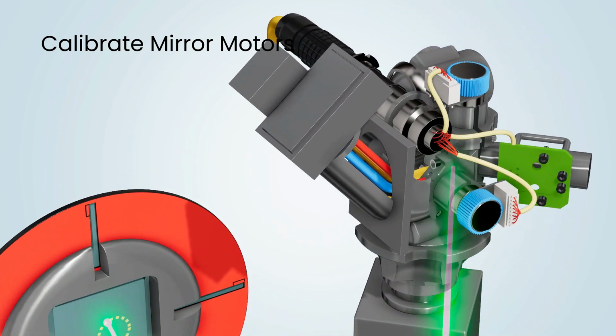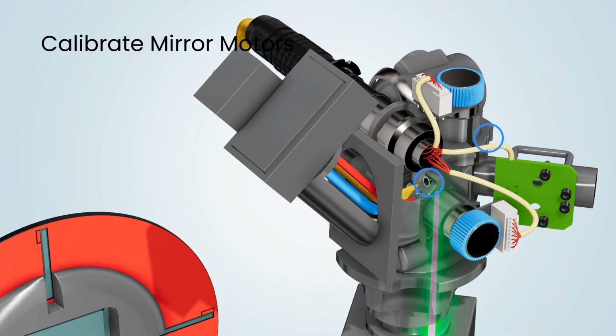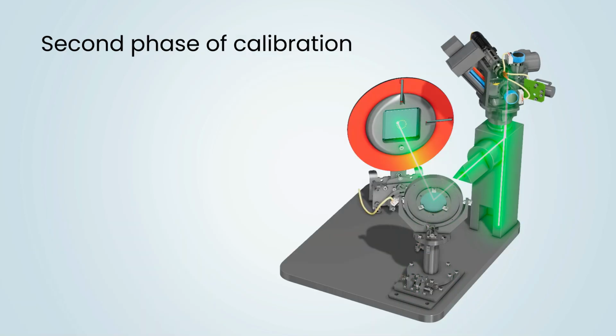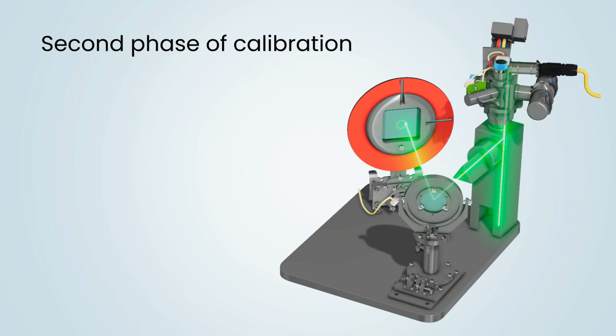Secure the motor's locking screws. This may affect the calibration, and the second phase of rotating the module on the target should be performed to verify that the laser remains centered on the target. If any adjustments are required, you must open the locking screws and repeat the calibration process until the laser dot drifts inside the target center while rotating the assembly and the locking screws are secured. Once calibration has been achieved, you can continue.